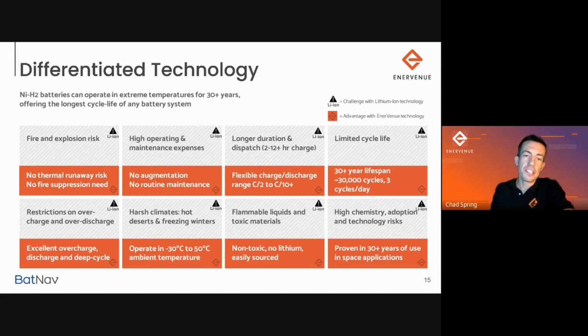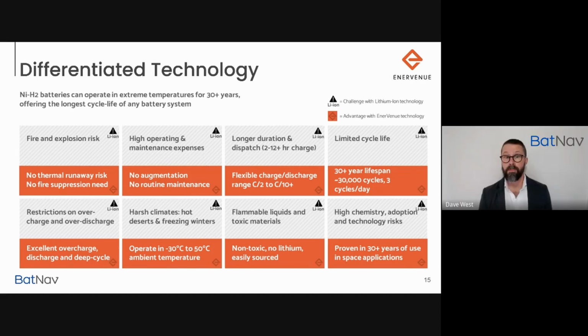Yes, but today's system is a 2-hour out to about a 10 or 12-hour system, and you can operate at varying C-rates depending on your use case of the day. Yeah, definitely, if you can get those C-rates up around the single-digit numbers, you can definitely do a lot of those ancillary services, which are high discharge, putting you in sort of the short duration grid services type market.